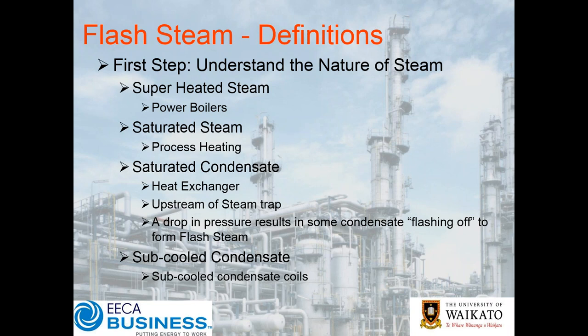When saturated condensate crosses a pressure drop, there's a drop in pressure, and some of that condensate will flash off to form what we call flash steam. In some applications you deliberately sub-cool the condensate below the saturation temperature, which in most instances means you won't have steam flashing off, though that does depend on pressures - we'll go through examples of that later.